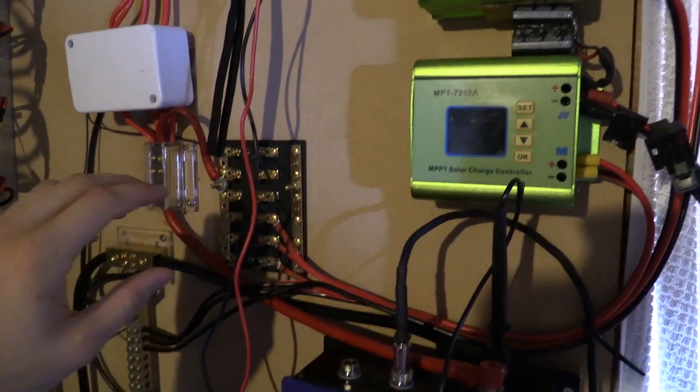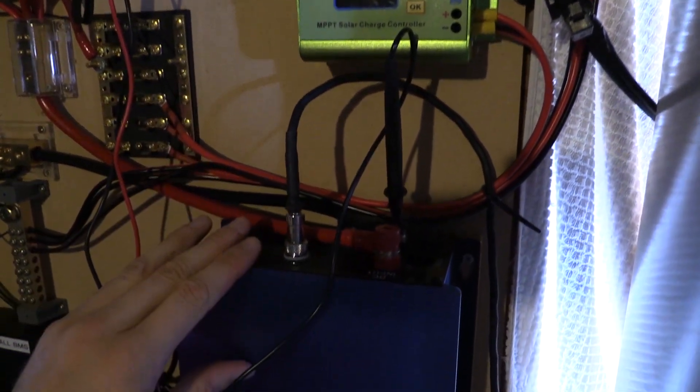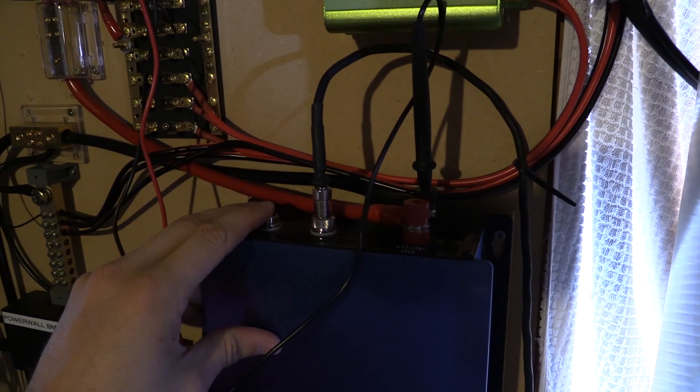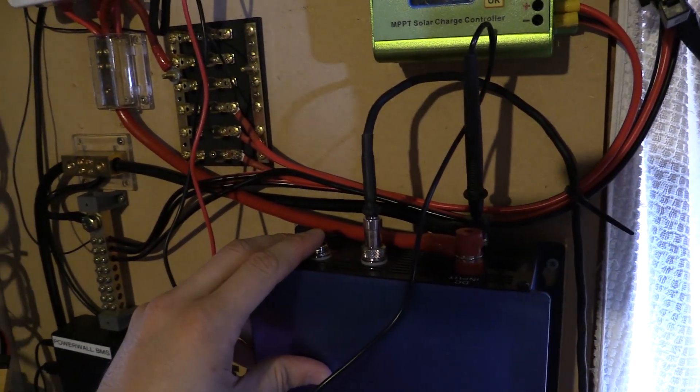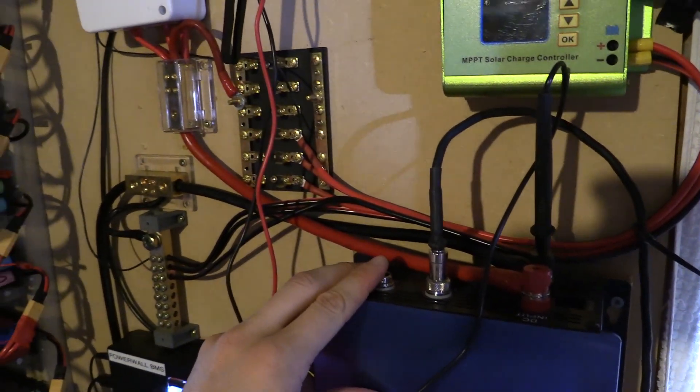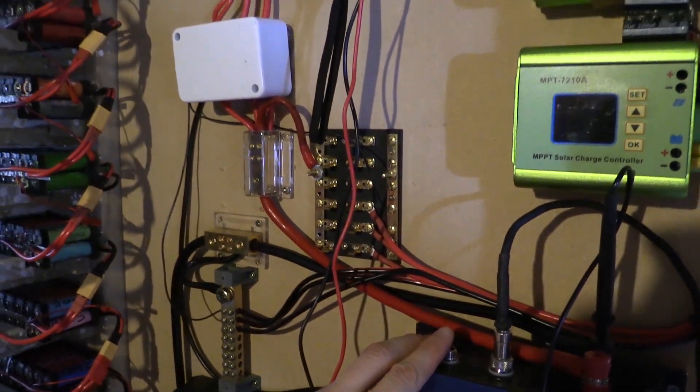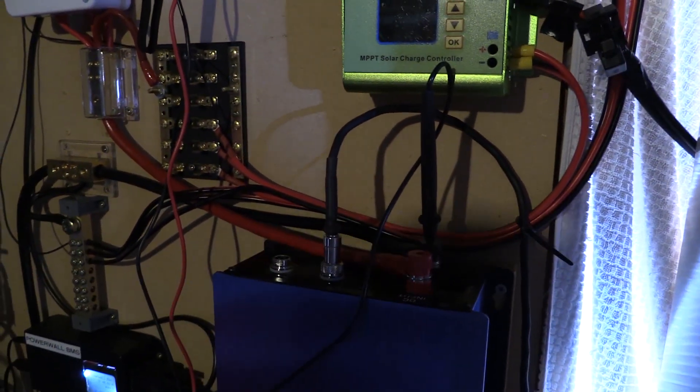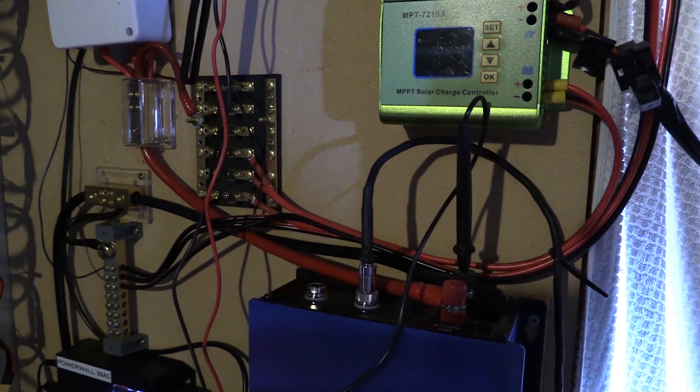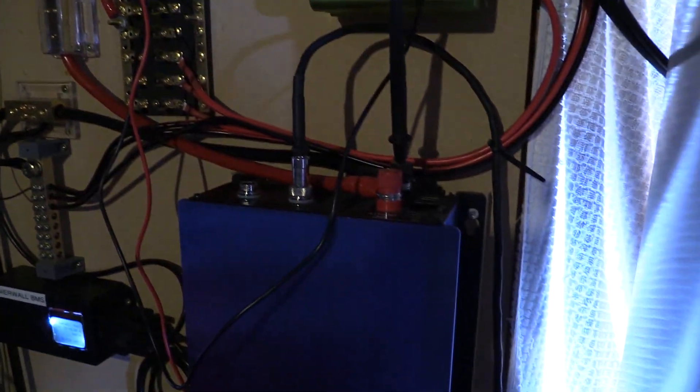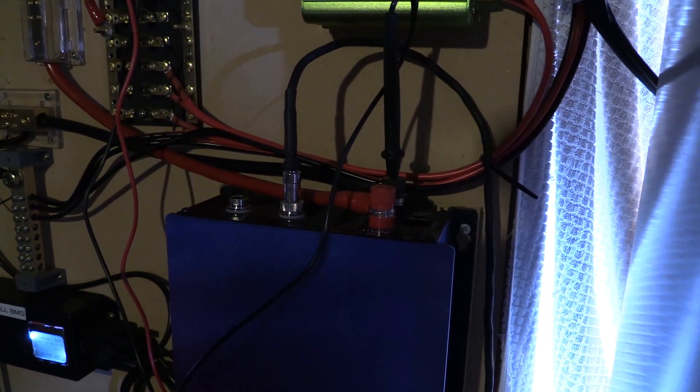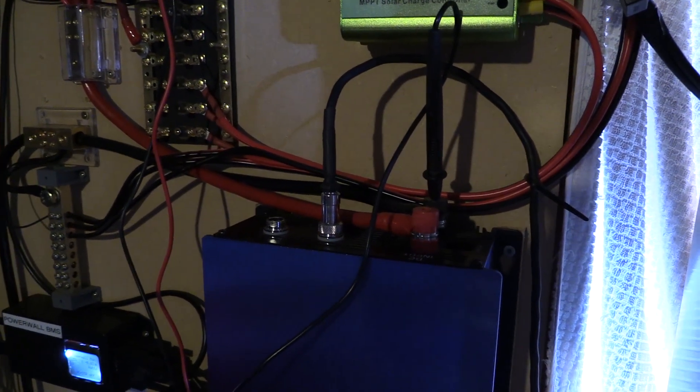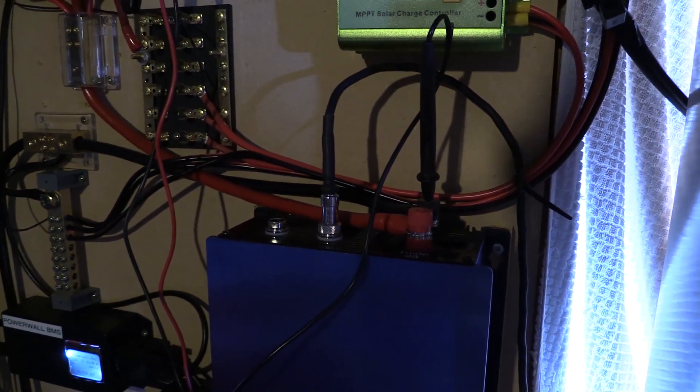With the grid tie plugged in, that's the only thing that could be causing the short right now. It looks like a dead short using the multimeter. The AC side of things seems fine, it's the DC side of things. Because the power was still onto it, it didn't blow a fuse there.